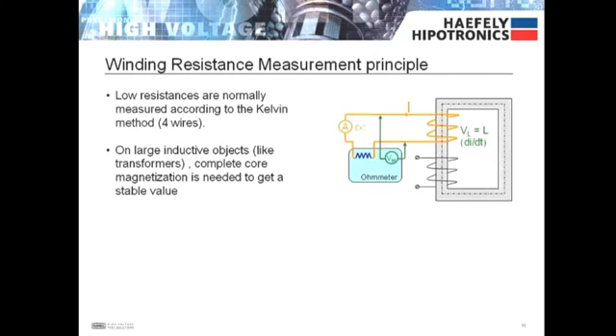The resistances are normally measured according to the Kelvin four wire method where two current leads and two voltage leads are used. A known current is introduced into the circuit and the voltage drop is measured. On large inductive objects like transformers, complete core magnetization is needed to get a stable value.